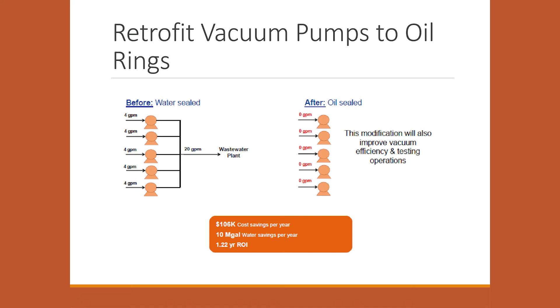And when we came in to do a water balance and look for areas where things could be improved, one of the facility managers had actually heard about a kit that could convert these pumps into oil-sealed pumps. And once the pumps were converted over, they had better vacuum seals and they ran more efficiently. So we saved 20 gallons per minute of water and actually improved the equipment that was available at the site. So total savings came out to 10 million gallons per year, which is a huge amount. And they saved $106,000 per year for a return on investment of just over 1 year. So that was a pretty quick success.